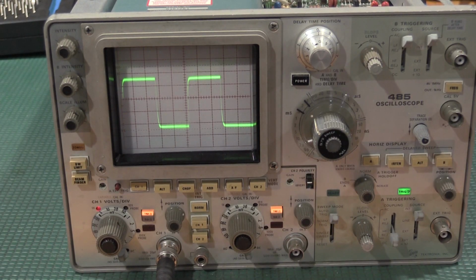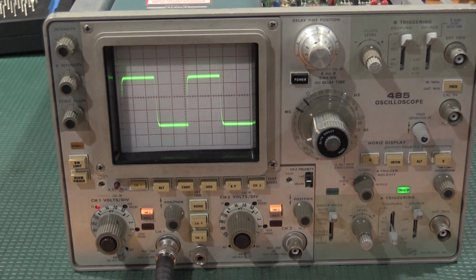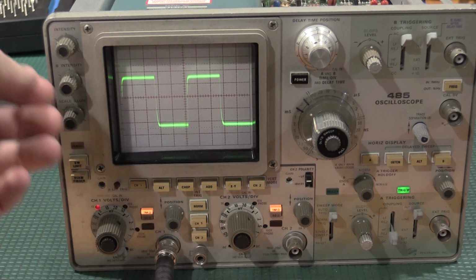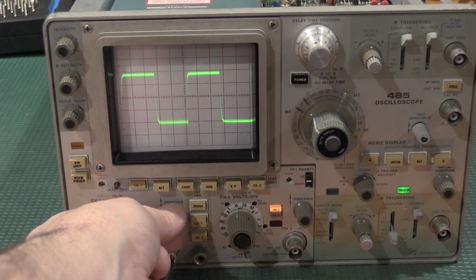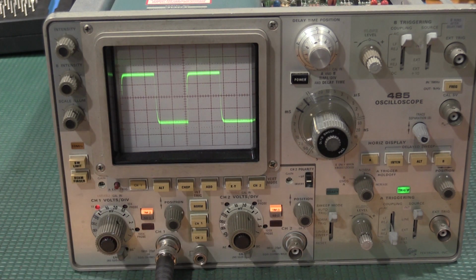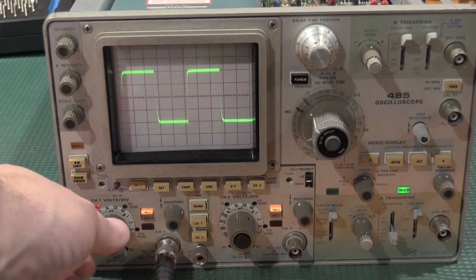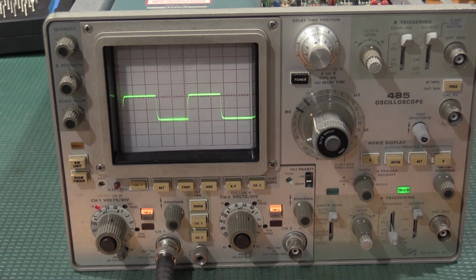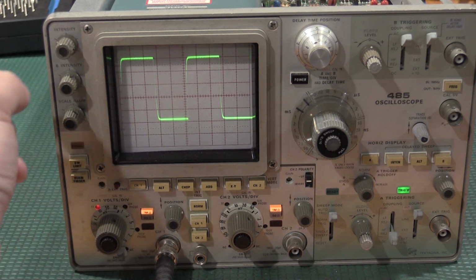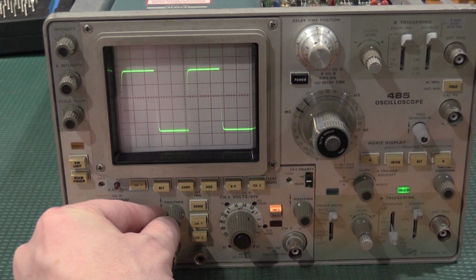All right, I'm hooked up to the calibration generator. We're on 5 millivolts per division. I am shooting 20 millivolts of signal into the front end. Obviously, we are off a touch on calibration. Not by much. Let's see. Yeah, it needs to be calibrated because that's 4% low, so just out of spec, but we're at its lowest range, so we'll kick it up. And let's see what we've got for...